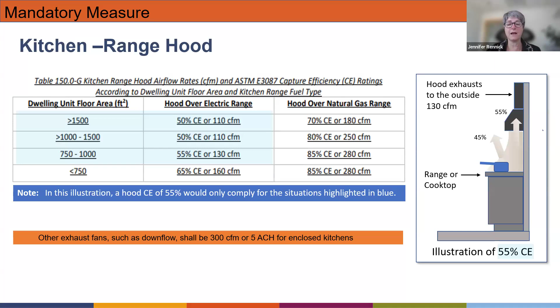And then the mechanical exhaust for the kitchens is to be field tested with the airflow hood. And you can follow the prescriptive method for setting up that duct system, such as the duct length is to be less than 25 feet and have no more than 3 elbows, and the exterior termination needs to have a proper fitting to protect it.